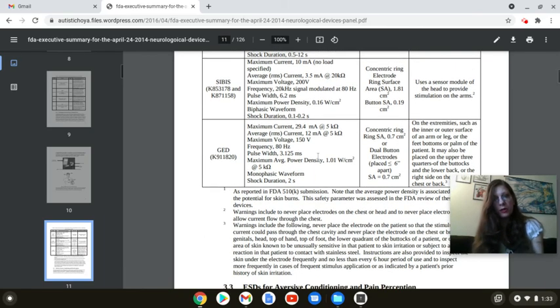GED: maximum current 29.4 mA at 5K. Average current 12 mA at 5K. Maximum voltage 150 V. Frequency 80 Hz. Pulse width 3.125 ms. Maximum average power density 1.01 W/cm² at 5K. Monophasic waveform, shock duration 2 seconds. Notice in any of those videos, those shocks went on for a hell of a lot longer than 2 seconds.